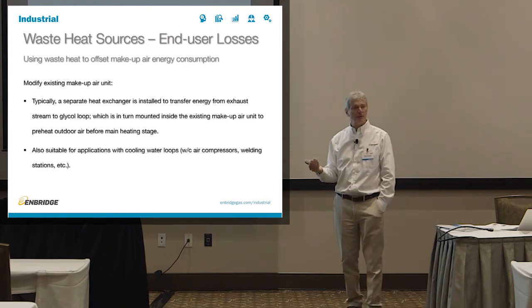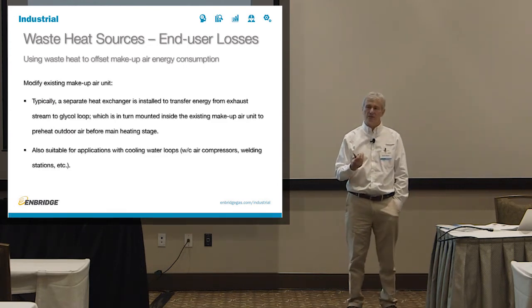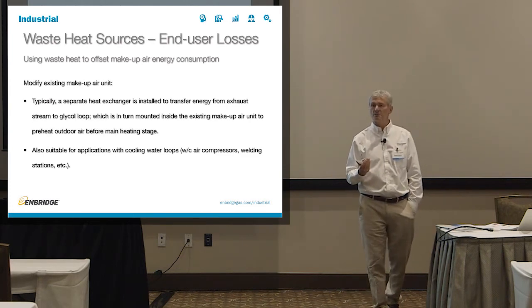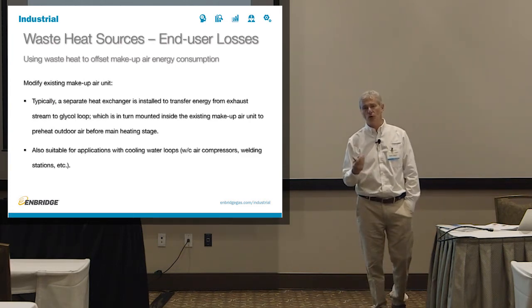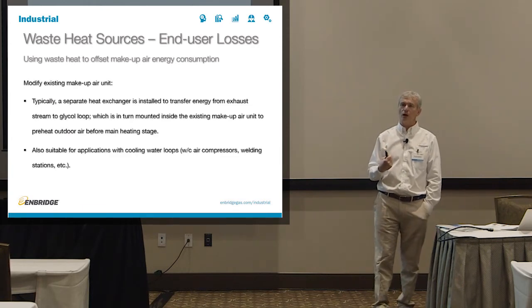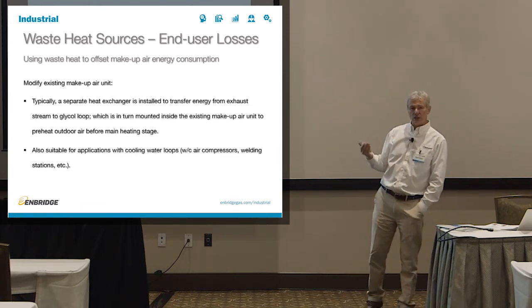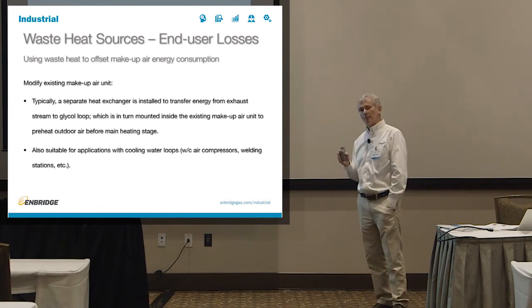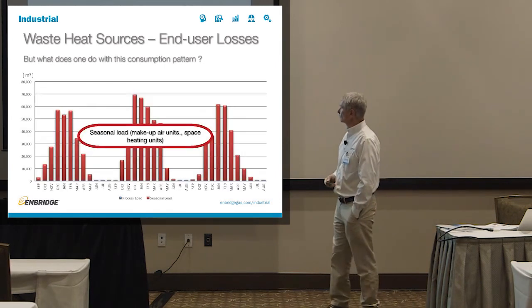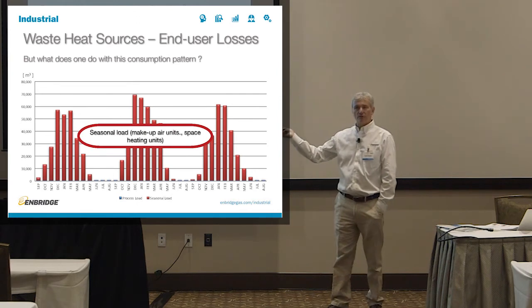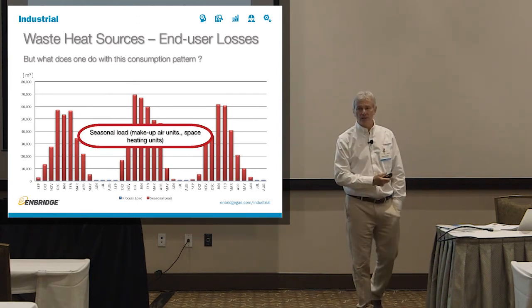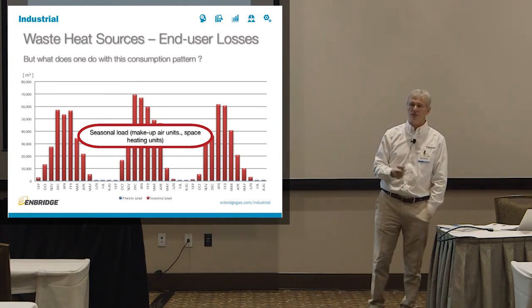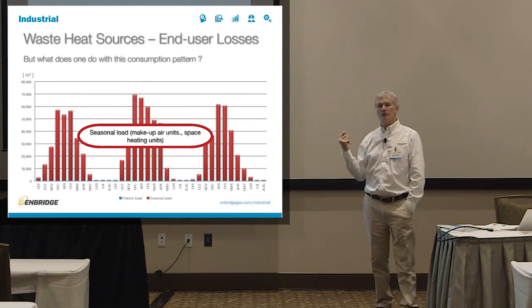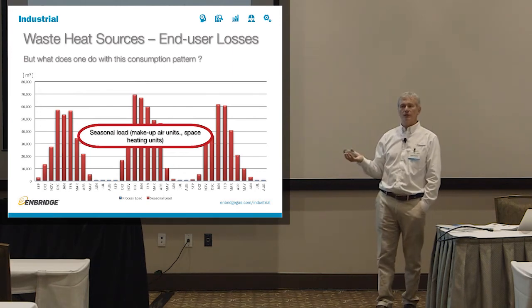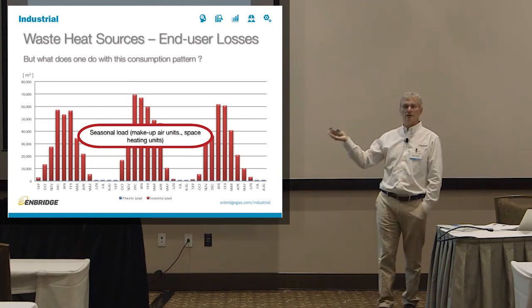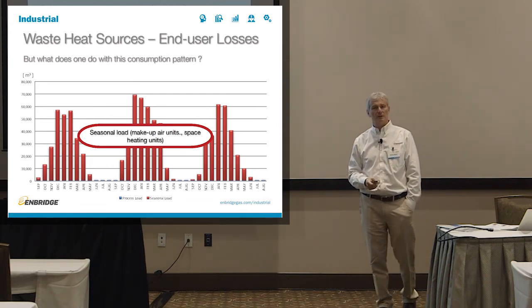That's a perfectly valid waste heat recovery mechanism. And for some people, it pays back in a very short period of time. For some, not, depending on your consumption, depending on how much makeup air you have. So we'll talk about it a little bit more now, about the makeup air side of things. Or if you have a facility whose profile looks like this. A lot of our facilities in our service territory look that way in their consumption. What to do then? You have no option but to use it in the seasonal load if you want to use some of the waste heat.